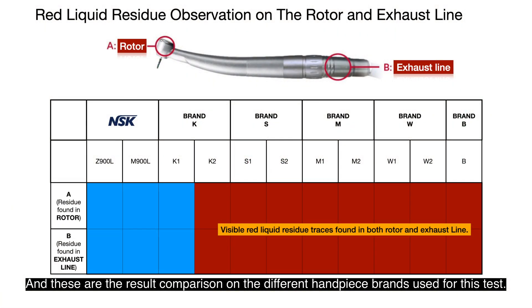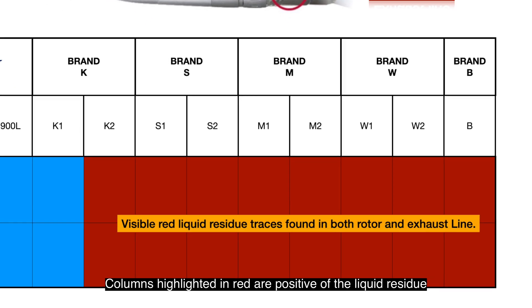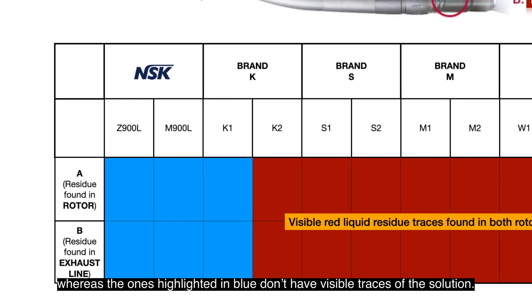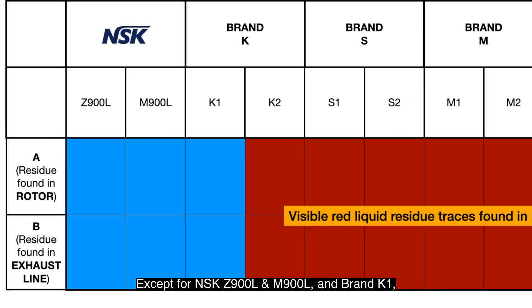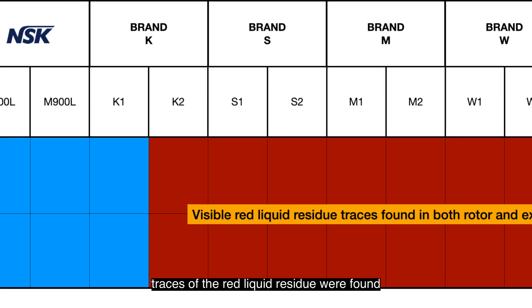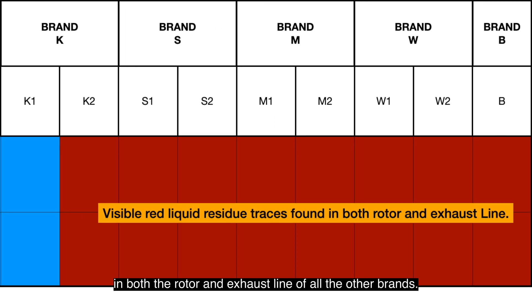These are the result comparisons on the different handpiece brands used for this test. Columns highlighted in red are positive for liquid residue, whereas the ones highlighted in blue don't have visible traces of the solution. Except for NSK Z900L and M900L and Brand K1, traces of red liquid residue were found in both the rotor and the exhaust line of all other brands.